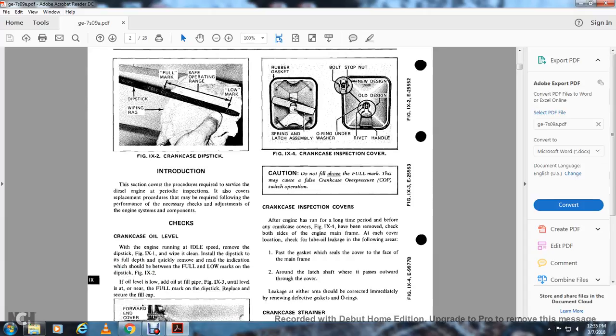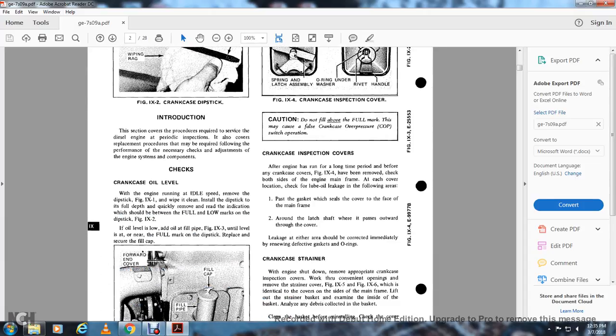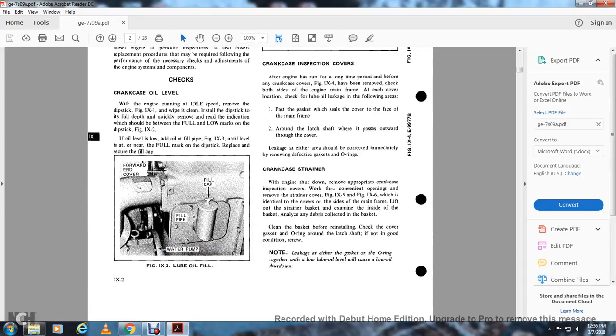Crankcase inspection cover: After the engine has run for a long period, before removing any crankcase cover (figure 9-4), check both sides of the engine main frame at each cover location. Check for lube oil leakage and air passing through the gasket and seals over the cover face of the mainframe, around the latch shaft where it passes outward through the cover. Leakage should be corrected immediately by renewing the defective gasket or O-rings.